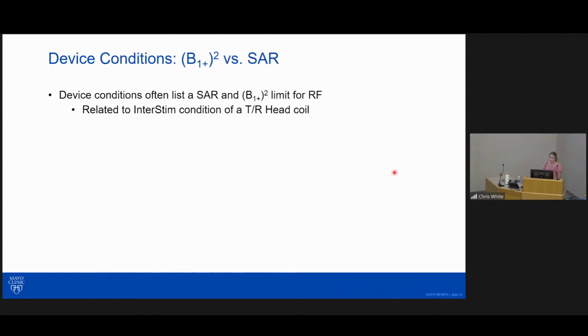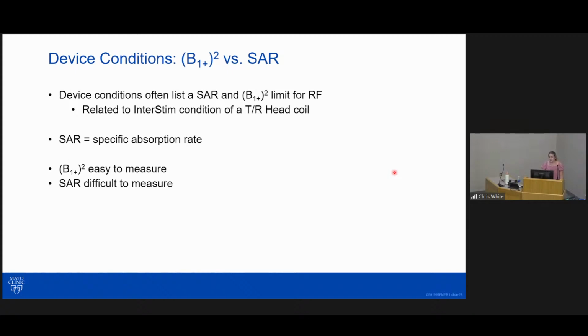Unlike the previous example, which specified a TR head coil, device conditions often list a SAR or B1 plus limit for the radio frequency, or RF. SAR stands for the specific absorption rate, and it's the rate of RF energy deposited in tissue. The spatial dependence of the B1 plus field is straightforward to measure, and the spatial dependence of SAR is not. Therefore, when assessing the MR conditions for compact 3T scanning, we want to know if we can use the B1 plus squared field to independently measure the RF.